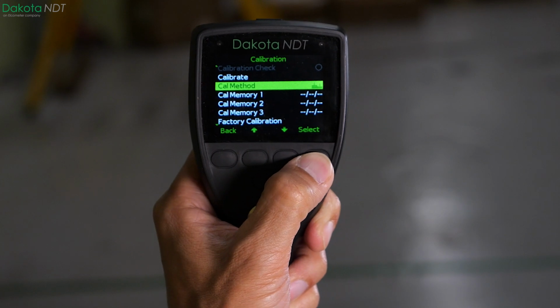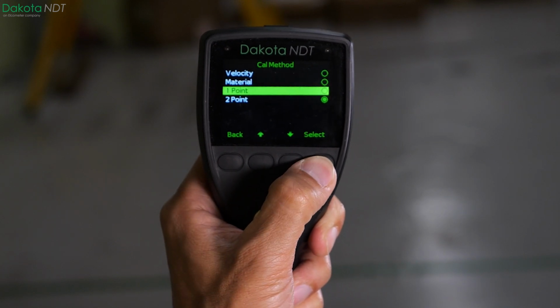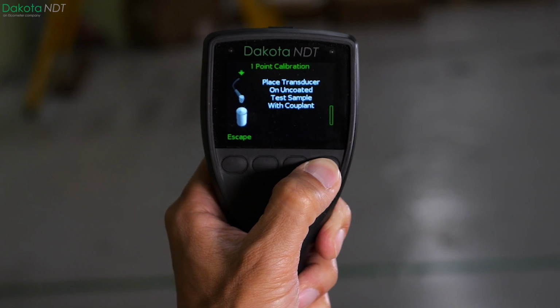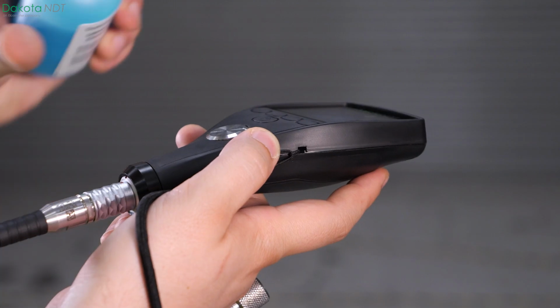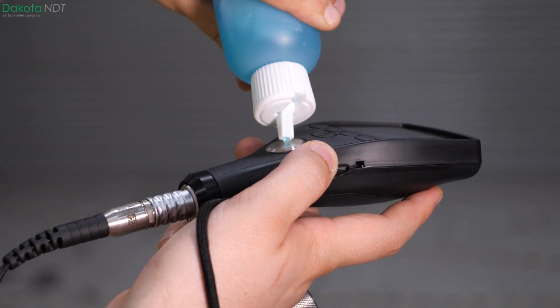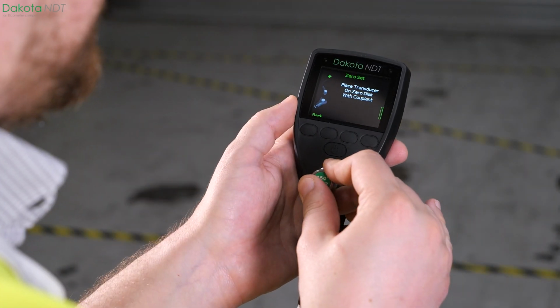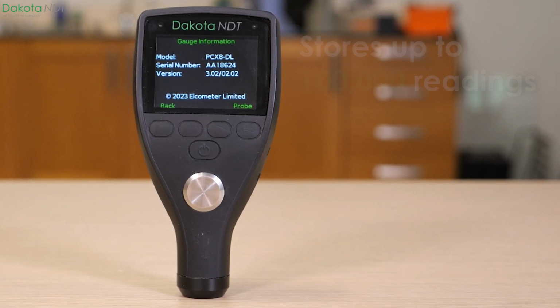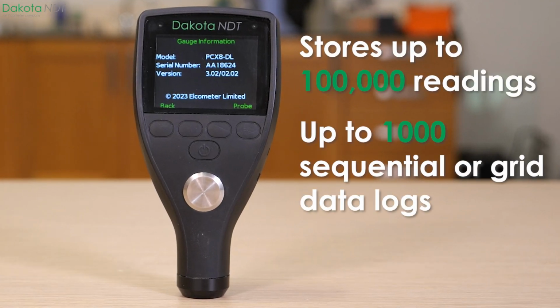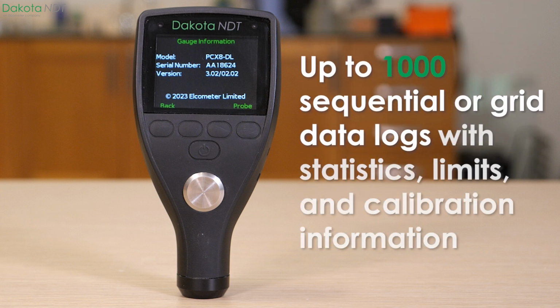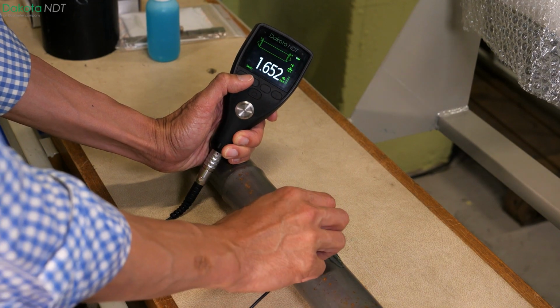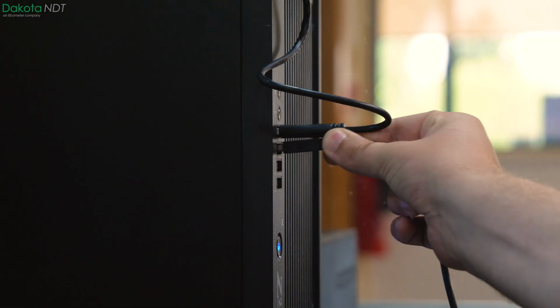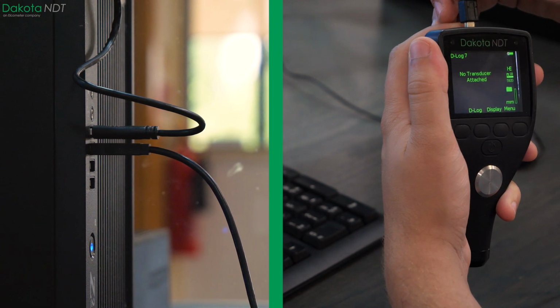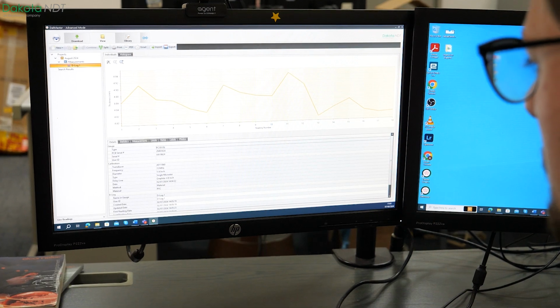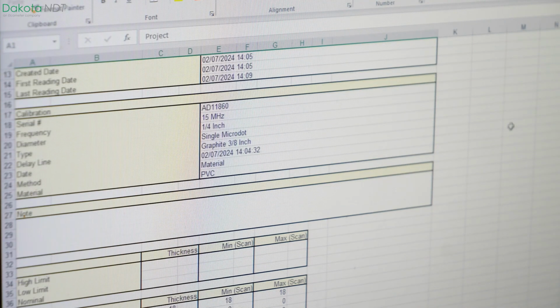The PCX8-DL has a range of calibration options, with simple, on-screen instructions that guide you through each method step by step. To find out more about all calibration methods, make sure you watch our Ultrasonic NDT calibration videos. Storing up to 100,000 readings in up to 1,000 sequential or grid data logs, along with statistics, limits, and calibration information, the DakotaNDT PCX8-DL can transfer all of this via USB or Bluetooth to ElcoMaster, our free application for PC, or into a number of common formats.